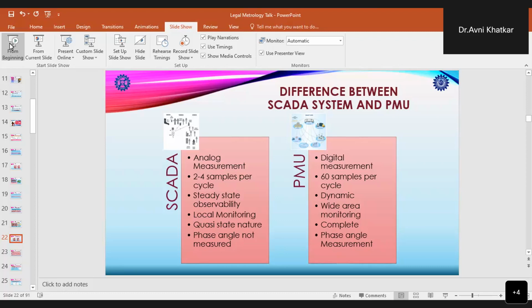And the PMU data which is collected can be used efficiently by the grid operators to monitor the real-time grid conditions and the phase angles so that we can optimize and push more power through the existing transmission lines and transformers. Hence, by using precise load balancing techniques, we can use the existing infrastructure to its maximum capacity. So by using a PMU, we are also getting wide area monitoring systems. So we are getting early warnings about our asset conditions, and a complete stability picture of the grid is there if we are using phasor measurement units.